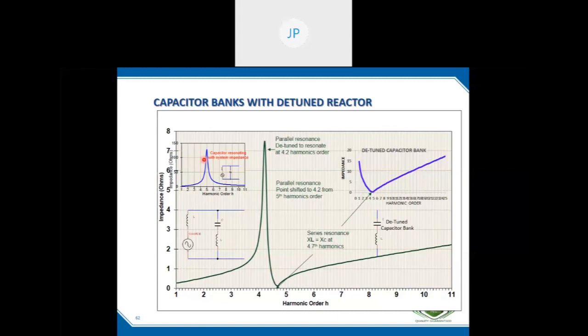4.2 is a safe point, there is no harmonic there, because for a 6 pulse inverter the lowest harmonic is 5. If there is a third harmonic in single phase loads, it may be the lowest one. Then instead of 4.7, we have to tune somewhere here, 2 point something, so that this point as a whole shifts like this.